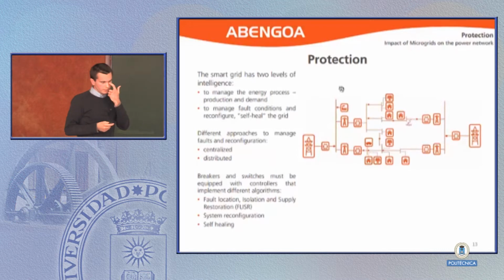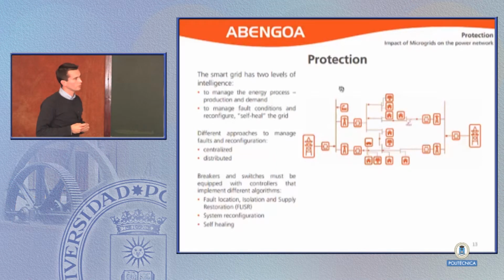The main task of a protection algorithm is that when a fault occurs, which can be an overcurrent or an overvoltage, the faulty section of the system is isolated from the healthy one due to the reconfiguration of the grid and changing the status of different breakers and switches. This reconfiguration is quite a challenging task in the new smart grid because of the distributed energy resources penetration, and the fact that the power flow can change the direction, and especially in a microgrid where we can have different aspects of the protection when operating in an isolated or connected mode.